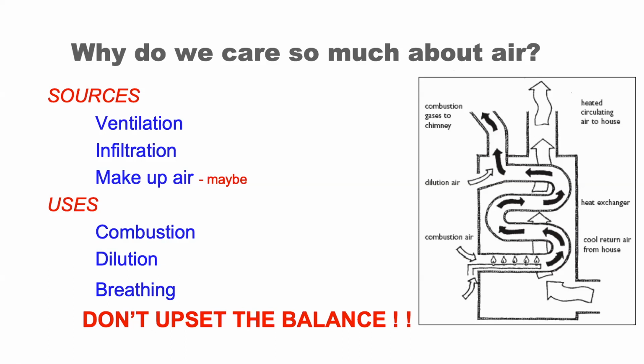So for example, ventilation air, I consider as air that's coming in purposefully with a mechanical system that's bringing fresh air into the structure. Infiltration is air that comes in through the leakage pathways. It infiltrates. It's not meant to be there, but it just happens. Makeup air sometimes is provided for combustion systems, other times it isn't.